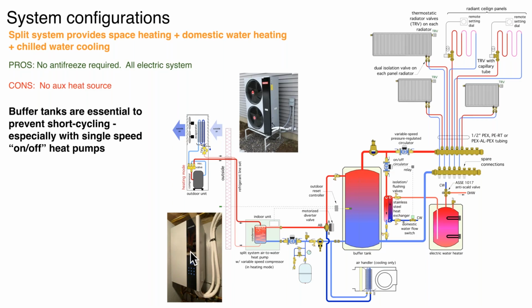It can be very simple, but you'll see there's a diverter valve here that basically takes the output from the heat pump, sends it to the buffer tank in the heating mode, or sends it to the coil in the air handler in the cooling mode. And again, over on the right side of the buffer tank, instead of internal coils for domestic water heating, we've got an external heat exchanger with a flow switch and a circulator. We've got a mixture of panel radiators and radiant floor circuits, all of which are individually controlled as independent zones using thermostatic valves, either valves that are built into the radiator or external valves that are connected to a dial with a capillary tube. So there's many, many different flavors or configurations of systems that we can build around air-to-water heat pumps. And we talk about that a lot in issue number 30 of Hydronics, as well as number 27. We show several different configurations.